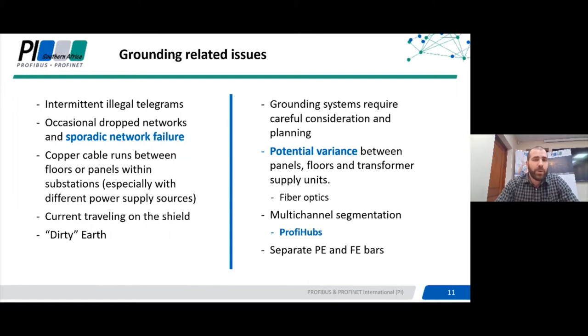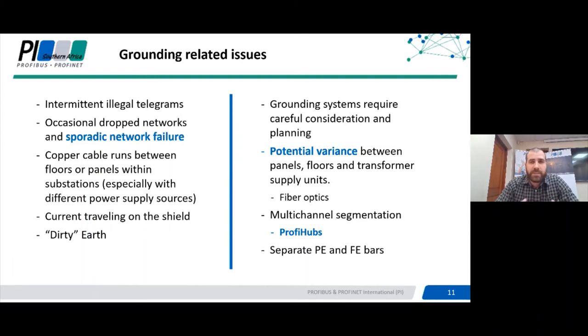The other type of grounding related issue is what I'd call a dirty earth, and this is where the discussion on functional earth versus protective earth comes in. Although they typically go to the same spike in the ground earth mat or transformer earth, you should probably have two separate cables to try to keep a clean high-quality earth and a separate protective earth, which would typically be noisy due to the components connected to it. Grounding systems require careful consideration and planning. Where there's a potential variance between panels, floors and transformers, utilize fiber optics where possible — especially when running between floors and different substations. Fiber optics will make your network completely immune to any potential variance issues.